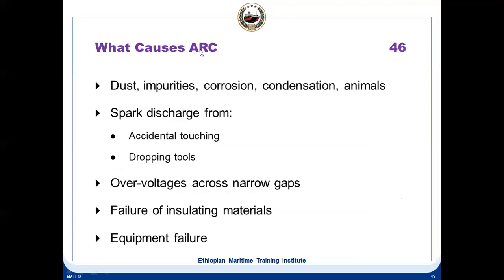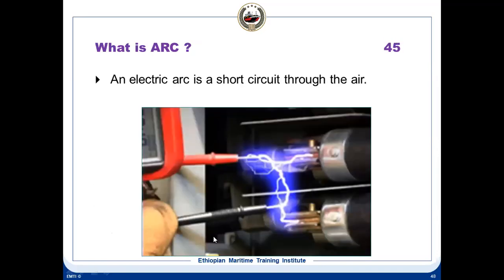Now, what are the causes of electric arc? It can be because of dust, impurities, corrosion, condensation, accidental touching, dropping tools, over voltage, across narrow gaps, failure of insulating materials, equipment failure. Suppose you have two phases here, R and Y. You touch, suppose by mistake you shorted these two. So that is an electric arc.